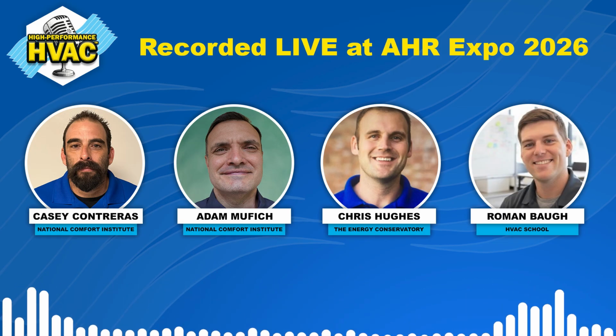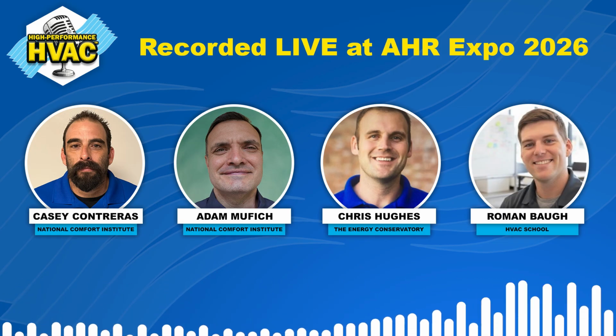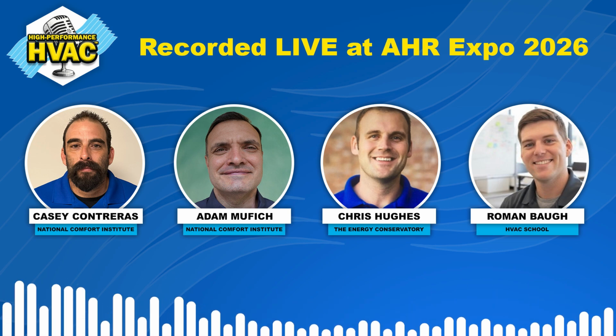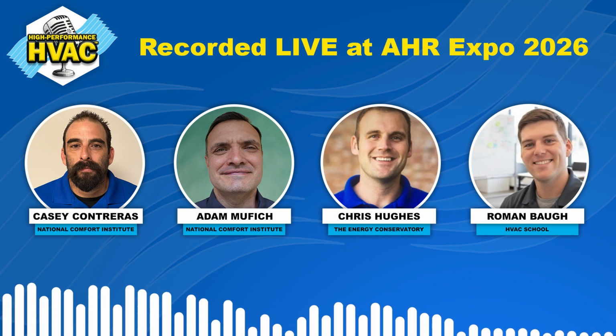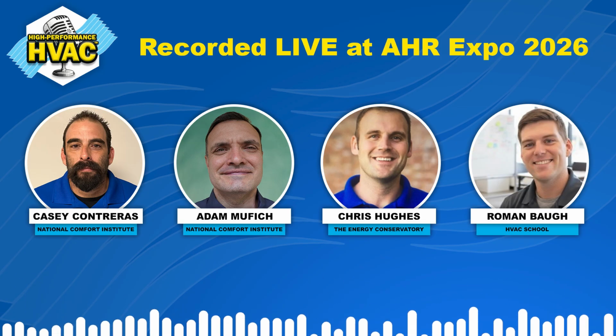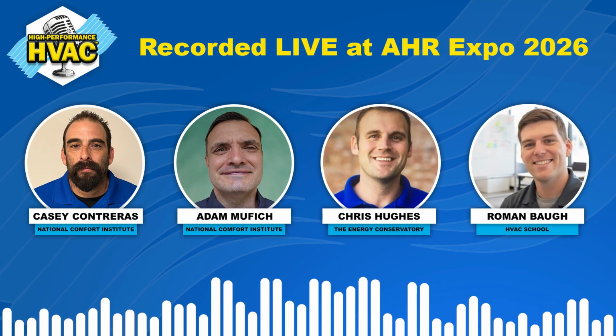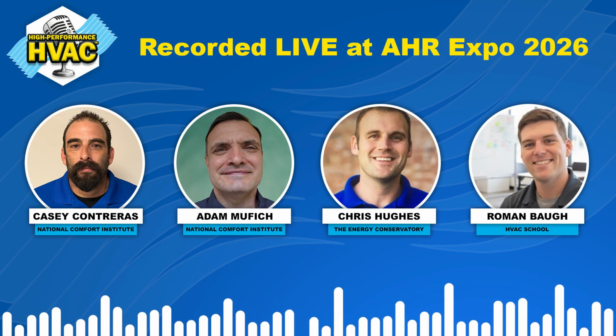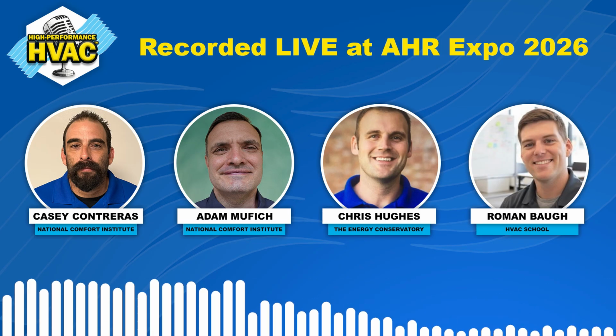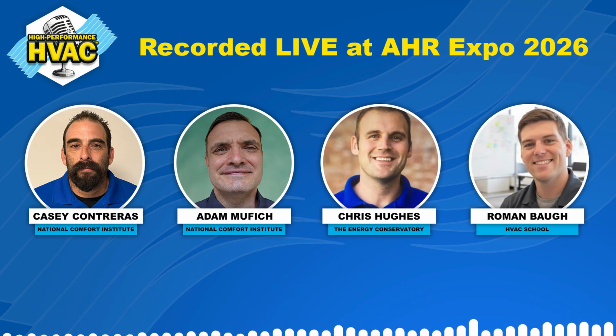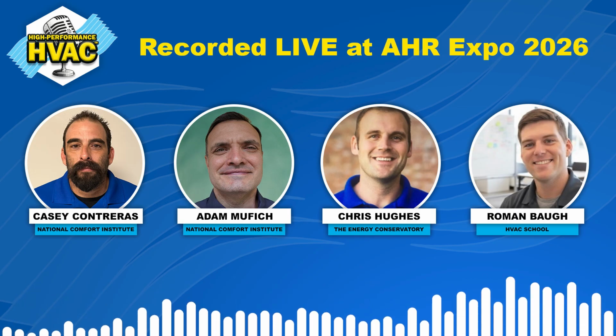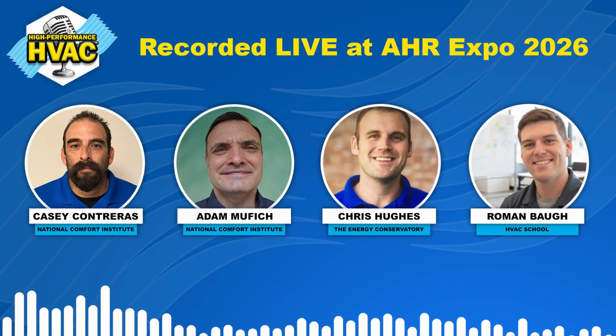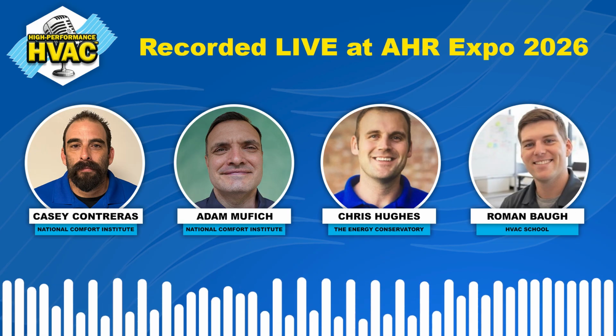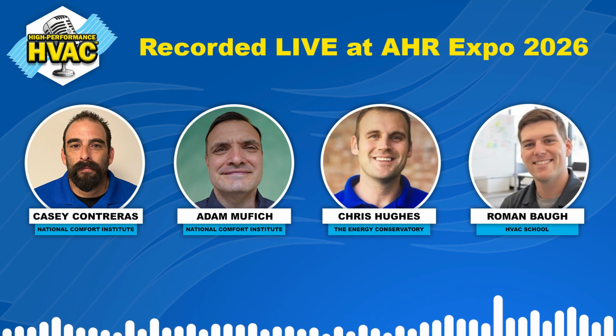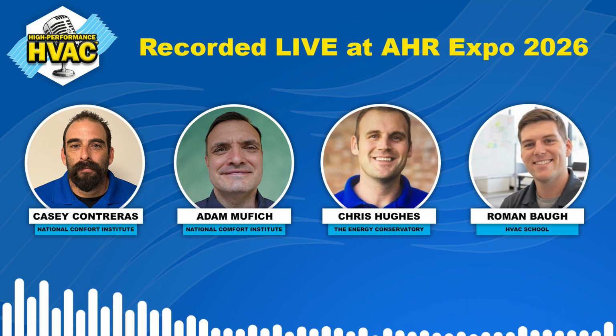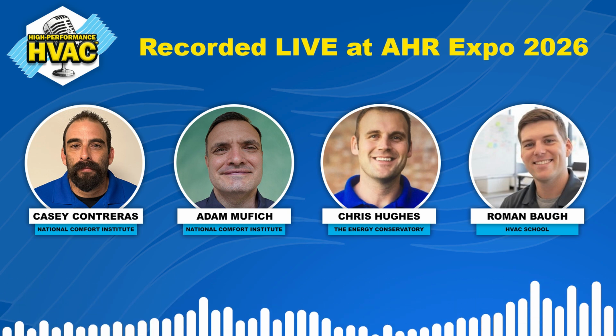I would think, and do they monitor, Daikin, you're a Daikin guy, but they're all the same, right? There's sensors all over the place. Do they have sensors monitoring the compressor temperature? Yeah. So yes. Can you tell if the heater is bad just by looking at the D checker? The further down the road we go with these systems and compressor manufacturers, mini splits, VRF, whatever it may be, they're putting thermistors on the compressor body, whether it's at the top or on the side, a little bit away from the crankcase heater, and you'll be able to see what is my compressor body temperature.